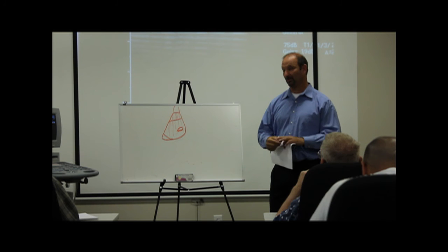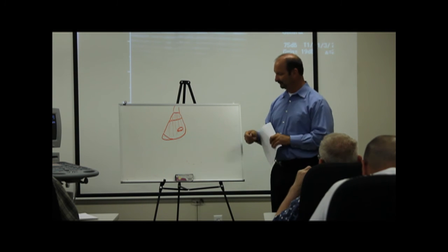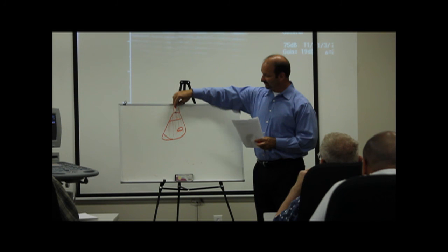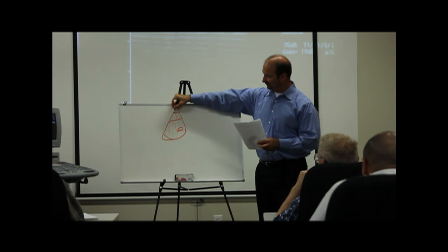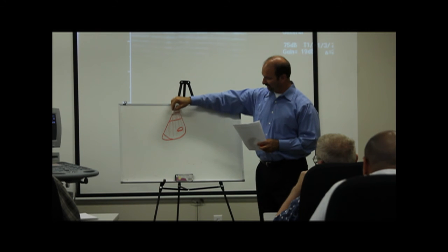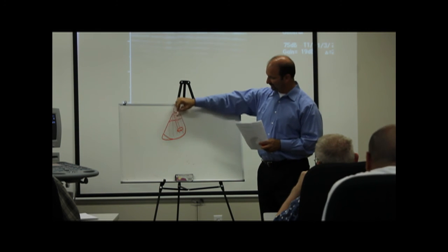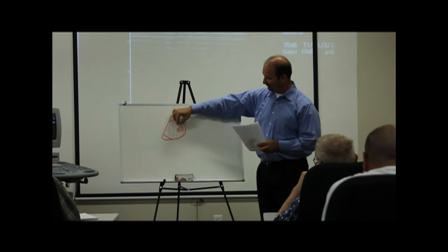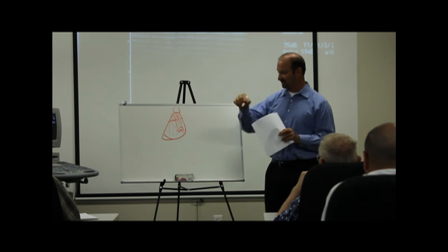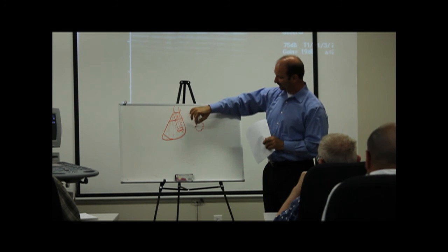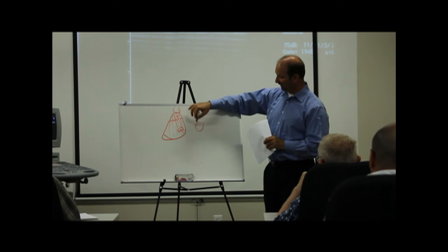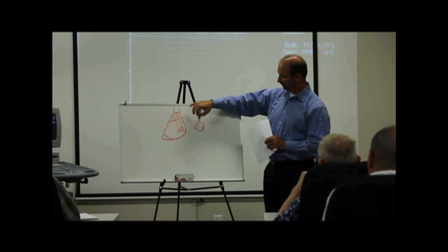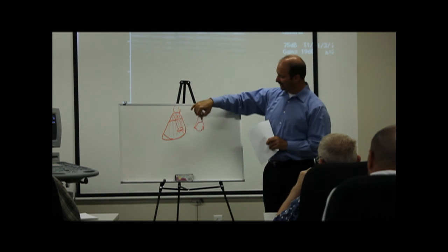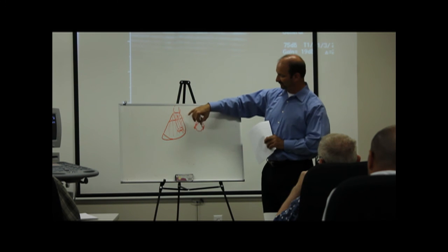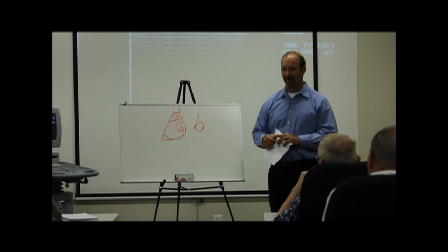Compounding can happen two ways. The most common way is that each one of these crystals will not only shoot up straight, but it'll shoot at an angle. So by compounding, we'll hit this way, start hitting it this way. You hit the same object from more angles, and you get better border detection down low. It doesn't really do anything for you up top, but you'll get better borders on the sides with compounding.